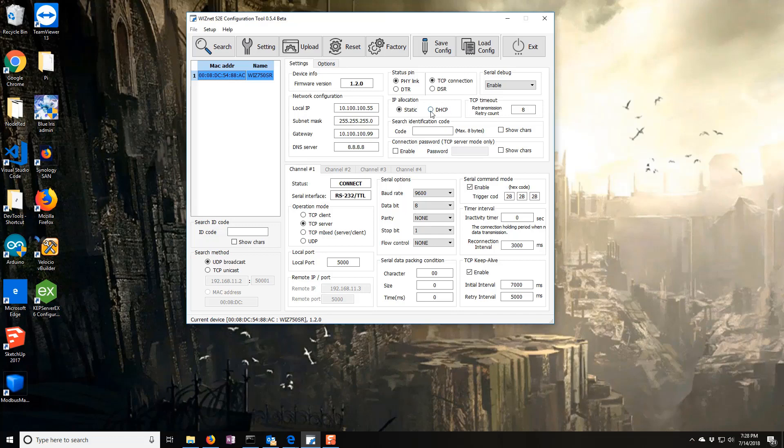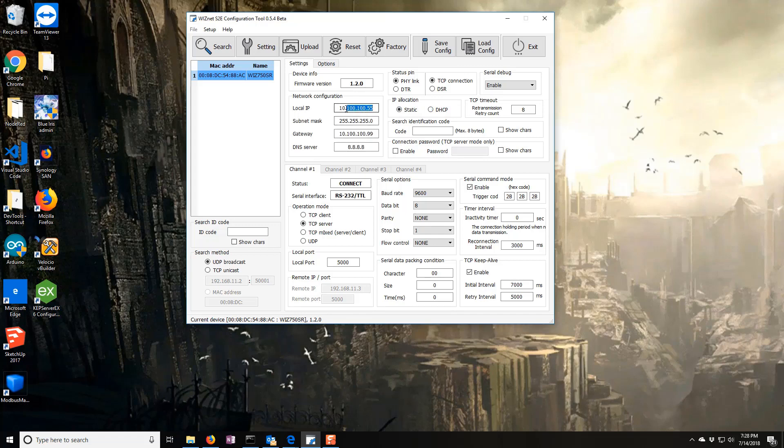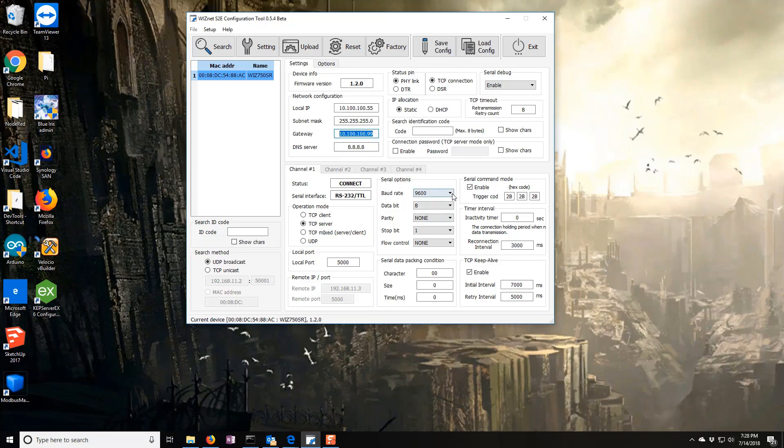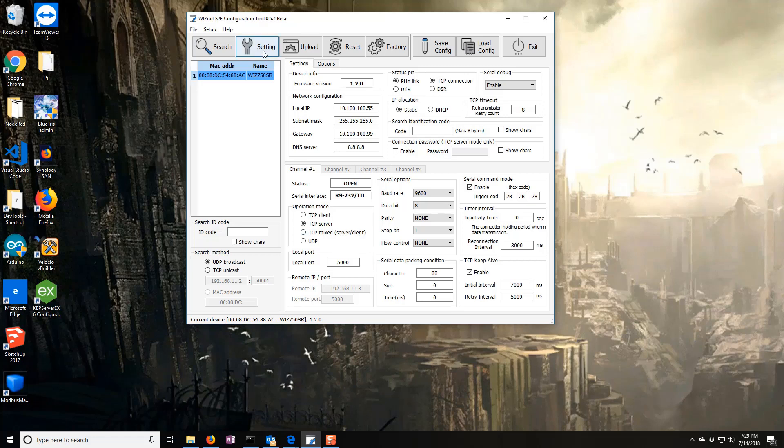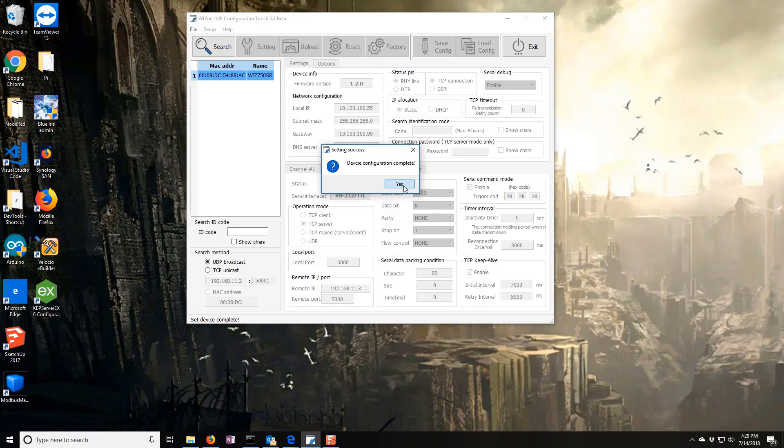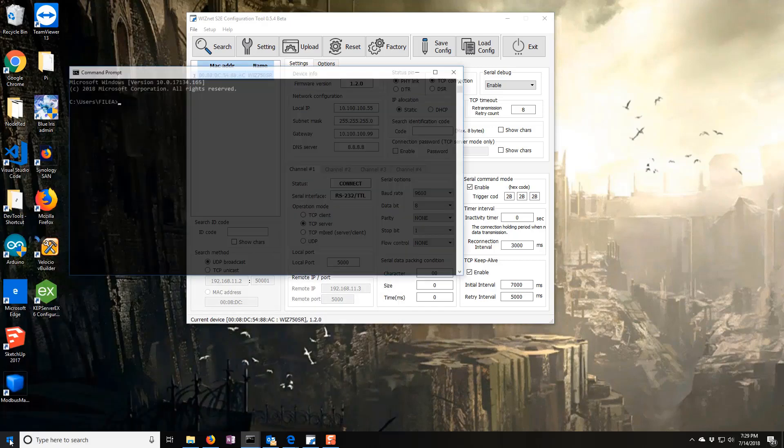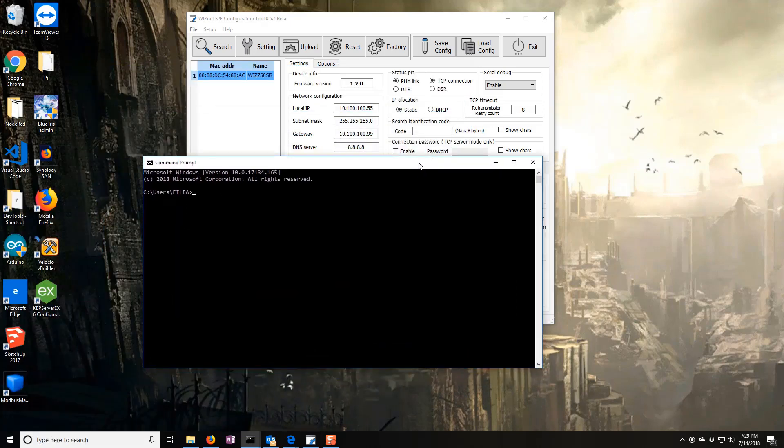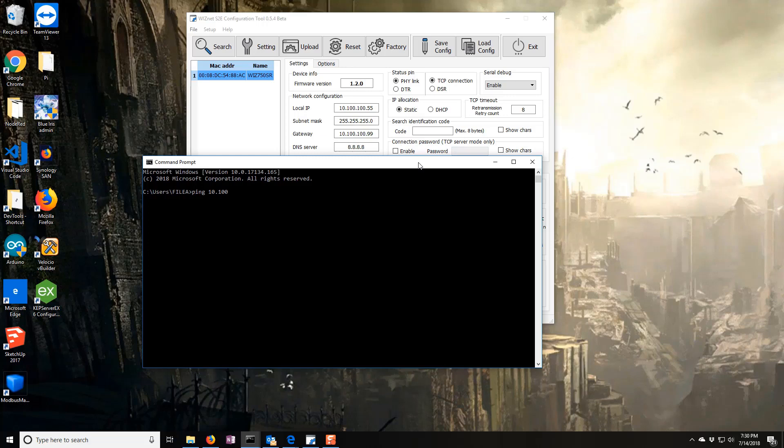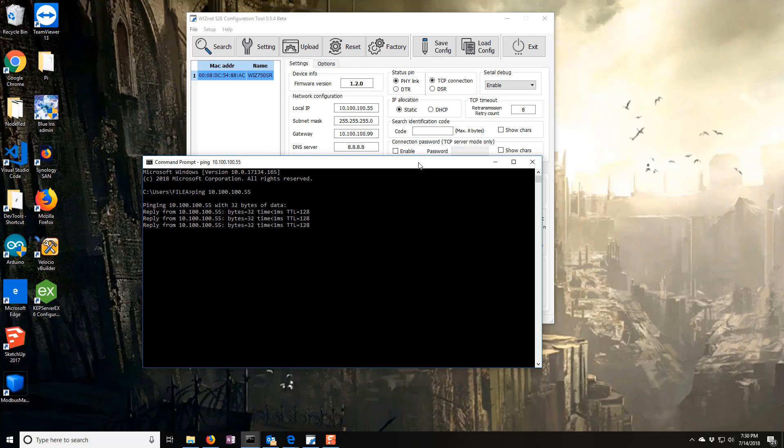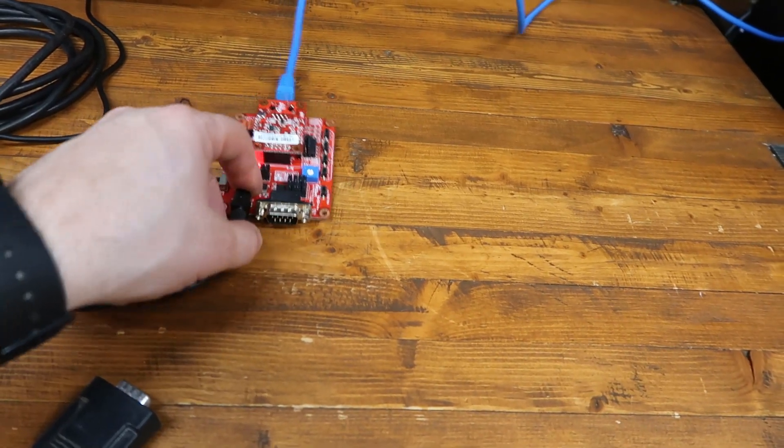So to configure it for my application, you could actually switch it to DHCP if you want. Instead, I changed the IP address. This isn't the IP address it comes up with initially. I put in the gateway. That's my router here in the building. The only other thing I changed is I set the baud rate. So my device wants 9,600 baud. After you've made the changes that you like, go ahead and click setting. And that goes ahead and loads your device. And after clicking that button, you can open a command prompt. And you should be able to ping the device with the IP address you just set. So it's live and ready to be connected. That's it.